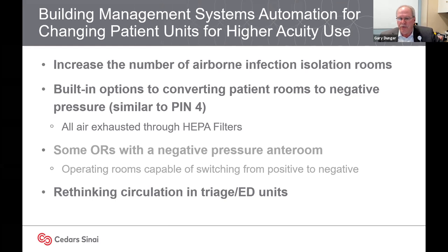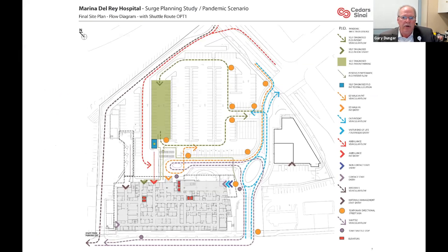A lot of consideration is being given to designing HVAC systems to be able to switch to 100% outside air and 100% exhaust. This has value as far as not recirculating air within the building. Also, in emergency departments or waiting rooms, the ability to do purge mode, or convert to 100% exhaust, while validating airflow patterns—because all this work is kind of useless if the airflow patterns get altered in a way that moves air in a direction you didn't intend.